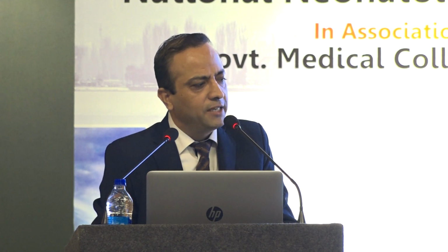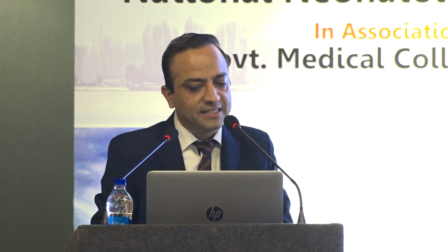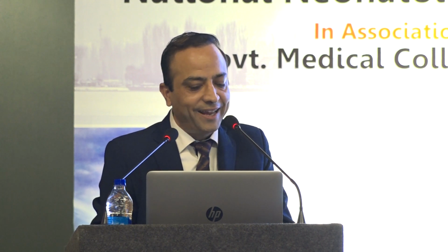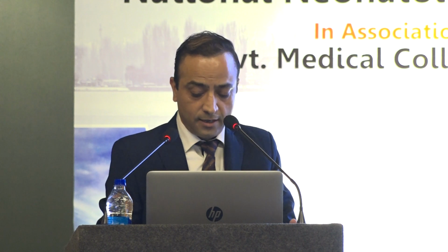Some of us may be using a more complex mechanism, which is the infant flow driver, where during inspiration, because of Bernoulli's effect and Venturi action, the air is driven inside, and during expiration, the work of breathing is further decreased because of fluidic flip of the direction of air, which is called the Coanda effect.